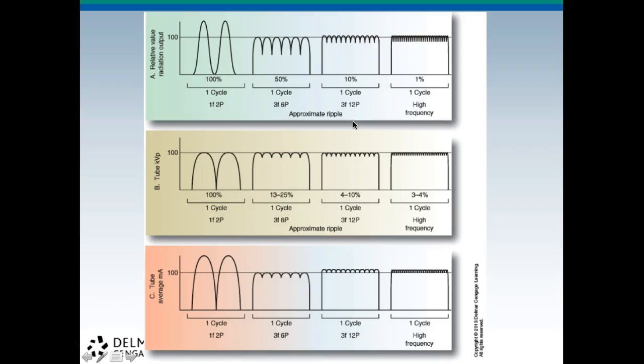So when we're looking here, we have single phase. So we have 100%. And then we go here, we have a 50%, and then we have 10% ripple, and this is three phase 6 pulse, this is 3 phase 12 pulse, and this is high frequency, so we're at a 1% ripple, which is great. So that's relative radiation output.